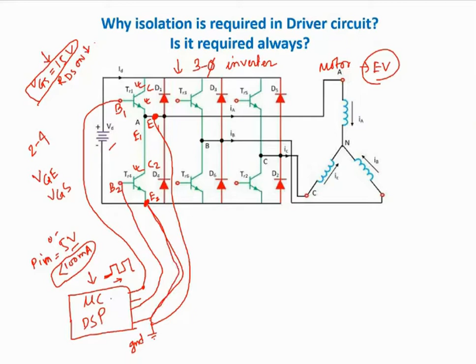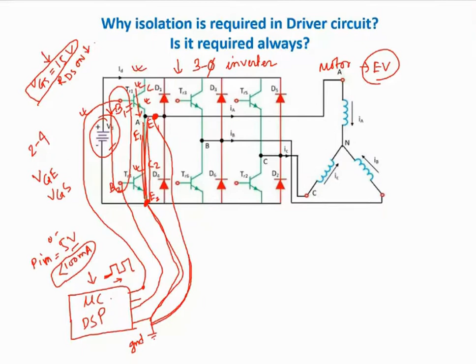Because both of their emitters are shorted. So as a result, as soon as you give a gate pulse to this device, when this device is turned on, this source is seeing a dead short. A very huge current will flow and your source may get damaged, this switch may get damaged. So this is the reason that in between you should use some sort of isolation.